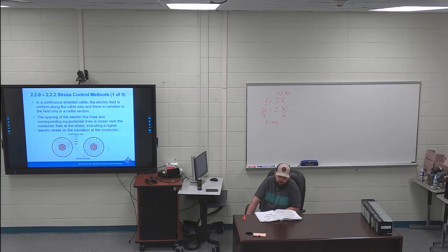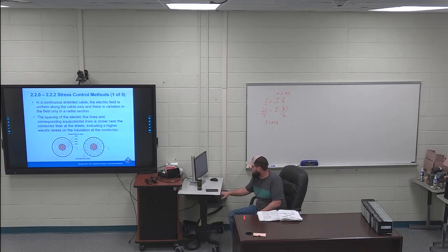Going on to 222. Capacitive stress control, first sentence is highlighted. This method consists of material possessing a high dielectric constant, generally around K30, and also a high dielectric strength. So that's, remember, a capacitor is just two plates separated by a dielectric, so that's the dielectric constant that they're giving. So generally it's in that K30 range. You got two questions for section 2 on page 28. I'm going to continue on to section 3.